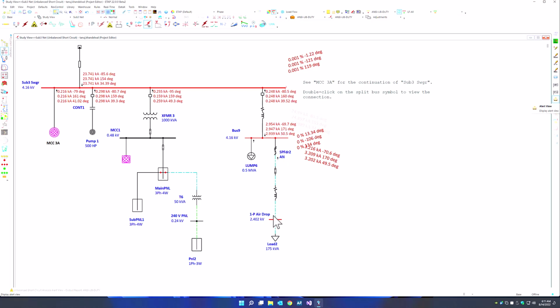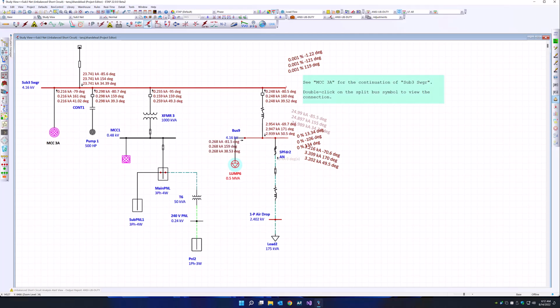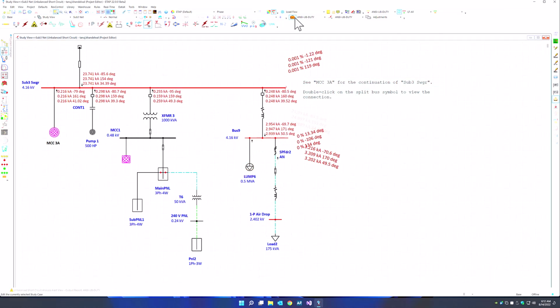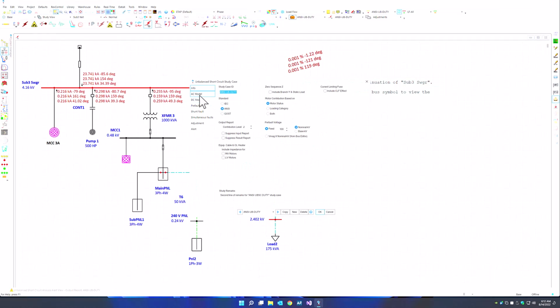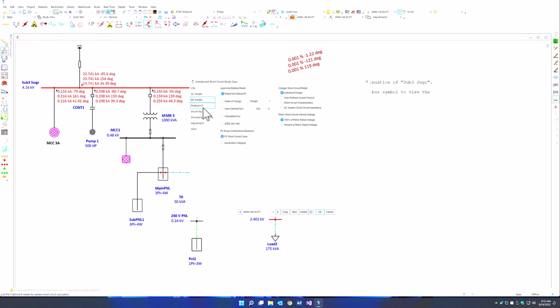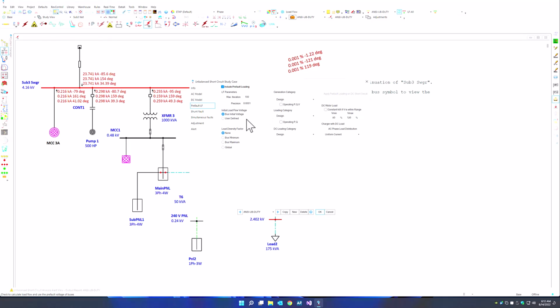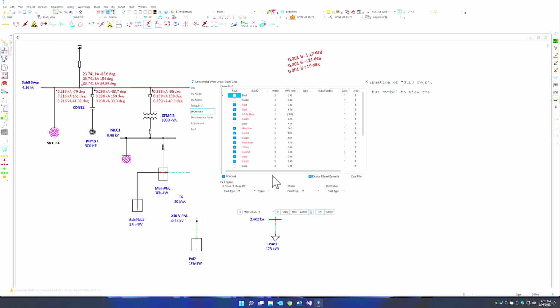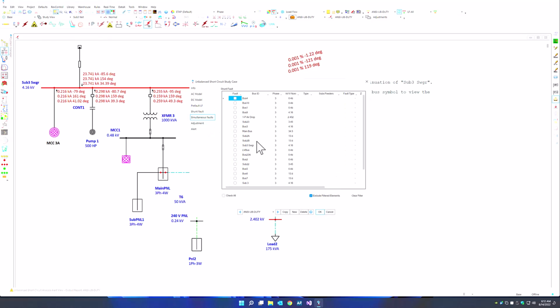In this case, you will see that there was no contribution from load 2 because this is a static load, or not a constant power load. But we can see lump 2 is actually a combination of a constant Z and a constant power load, and therefore there is actually some contribution from this piece of equipment. Inside the study case, you can choose between the AC modeling and DC modeling. You can also set up options for your pre-fault loading right before the fault inception. Select which buses are included for shunt faults, and of course which buses are to be included for simultaneous faults.